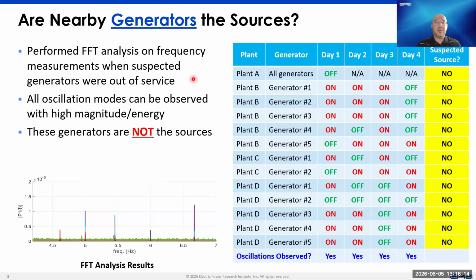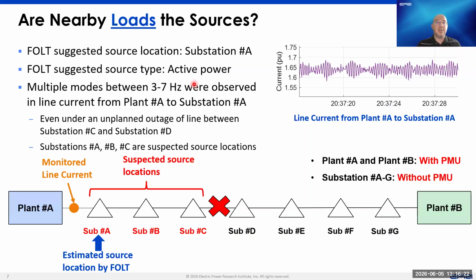So we had to continue the investigation and look at other potential candidates for introducing oscillations. Then we started looking into the loads as suspects. Here, at the bottom of the slide, you see a simplified single line diagram of one portion of the system. In this case, this is where we started using the tool that I mentioned before, the EPRI FOLT tool, using voltage, current, and frequency measurements. The tool estimated a specific substation as the source for the oscillations.